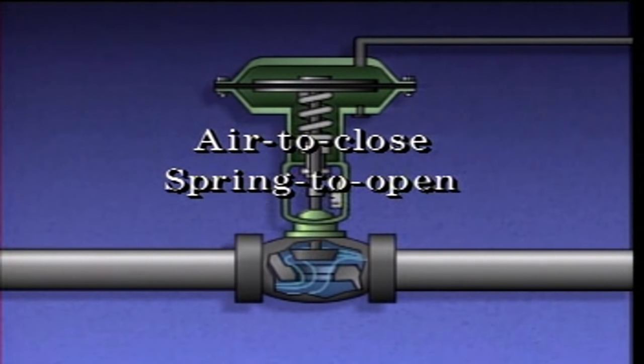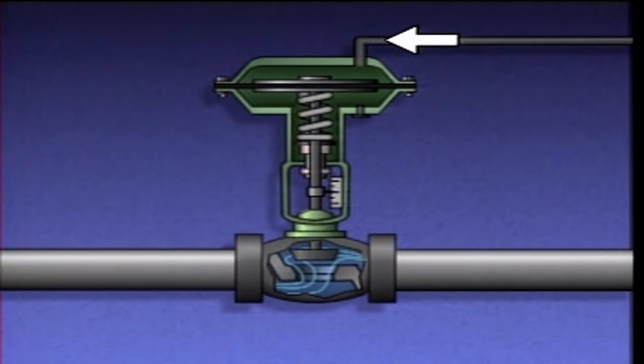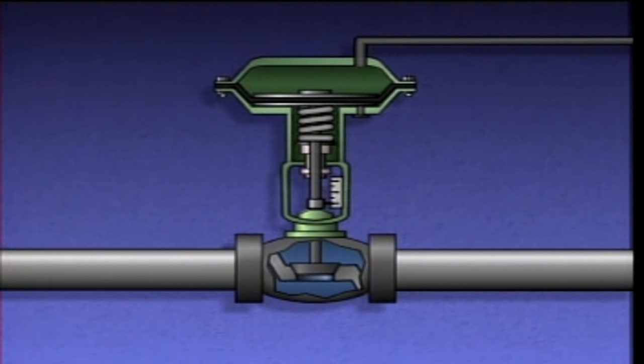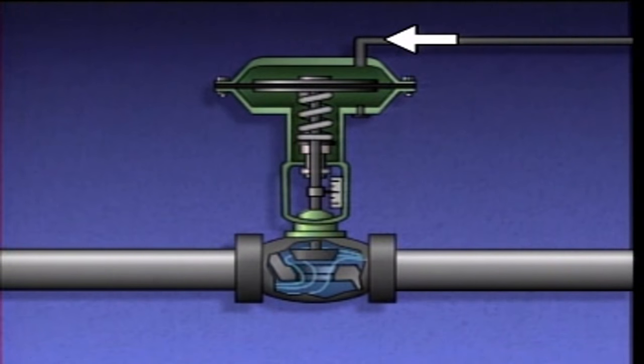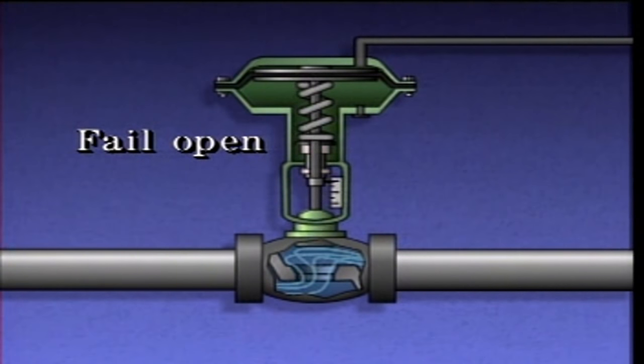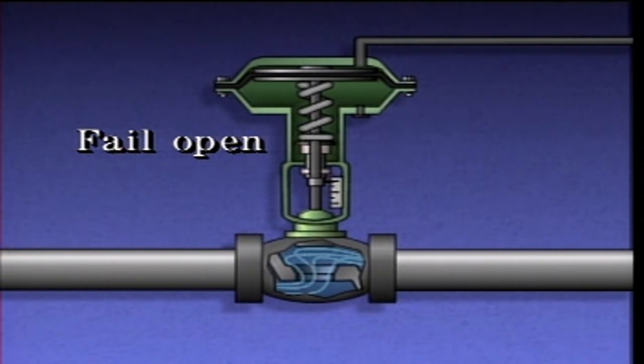This type of actuator can be called an air-to-close, spring-to-open actuator because air pressure moves the stem to close the valve and a spring moves the stem to open the valve. This means that if air pressure to the actuator is lost, the control valve connected to the actuator will fail open.